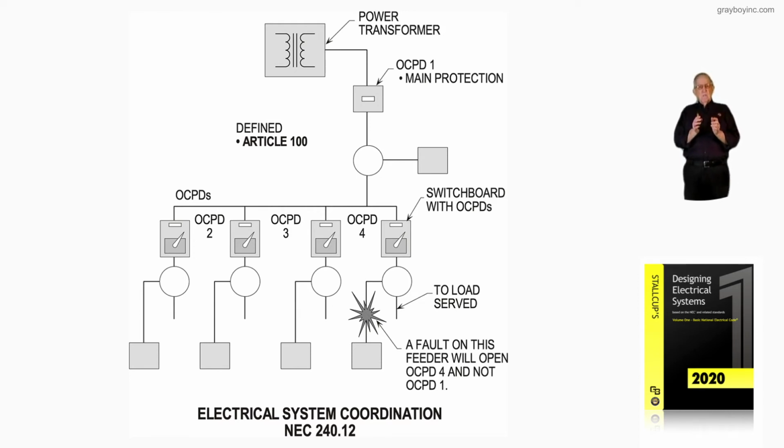And many times I'd have selective coordination without going through a lot of calculations. But this is a rule of thumb, and some breakers wouldn't work on this, sometimes like Federal breakers, Bulldog breakers, Zinsco breakers. So a little common sense should be used here.